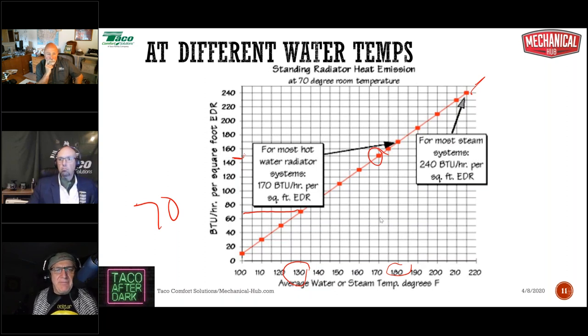What happens with lower average water temperature with cooling fans, forced convection and baseboard? What happens if the required flow rate is less than 1 gallon a minute for sizing baseboards for a space? Well, that would be a room with a heat load of less than 10,000 BTUs. 1 gallon a minute is about 10,000 BTUs. If you had something that low, yeah, the output would be a little bit lower.